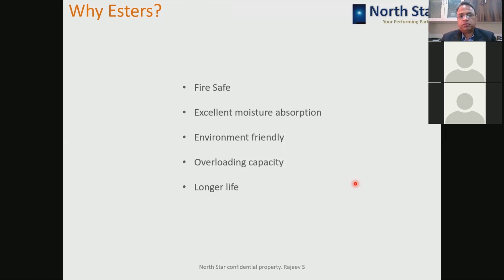So, considering all these things, synthetic and natural esters offer great fire safety, because of their high flash point of the order of 300 degrees centigrade, which is more than double that of mineral oil. They are comparatively much fire safe as compared to mineral oil. I'm not saying fireproof; they are safer than mineral oil because they will catch fire at a temperature of 300 degrees centigrade, whereas mineral oil will catch fire at a temperature of around 140 degrees centigrade.